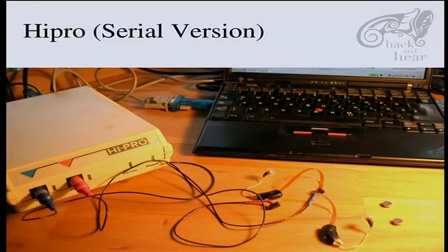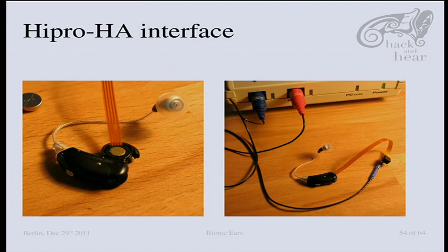Yeah, of course, some of this hardware ended up in my hands. This is a serial Hipro. It looks really fancy, like a modem from the 80s. It's connected via serial, and you connect the hearing aids to it. I have some closer pictures for that. So you take out the battery and put in a small cable which has a contact the size of the battery, a very flat cable, and this is connected to a bigger cable, and that is connected to the Hipro.